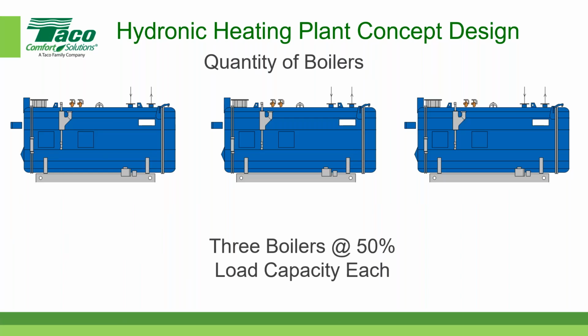You could have each boiler at 50%. That implies that you only need to run 2 out of the 3 boilers. Actually, that's our configuration in Cranston. We have 3 boilers in the basement mechanical room, each one sized for 50%, so that at any one given time, if one boiler should be offline, you have 100% capacity. The other option is to have 3 boilers at 33%. So if you lose a boiler, you have roughly 66% capacity.